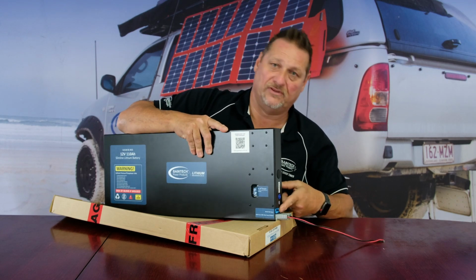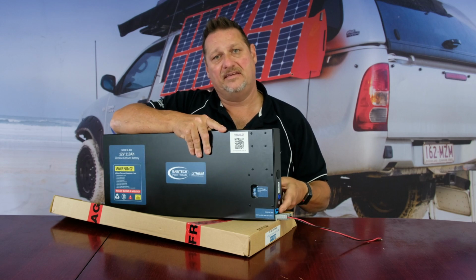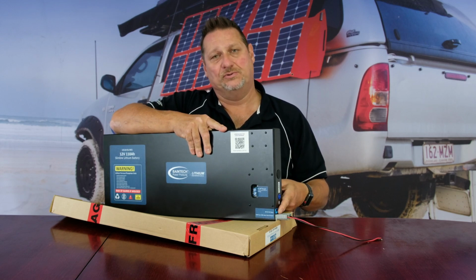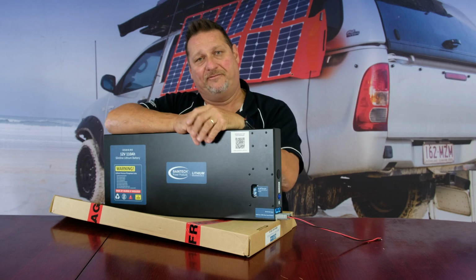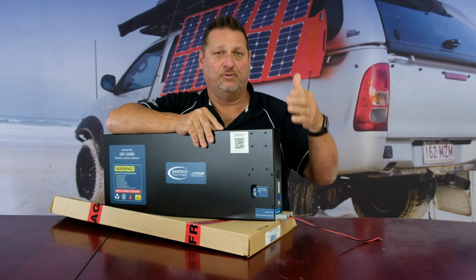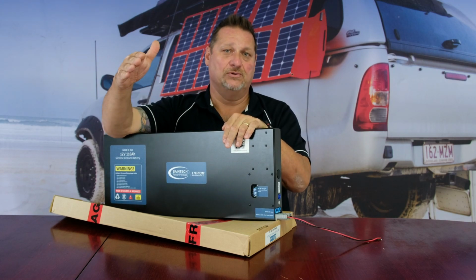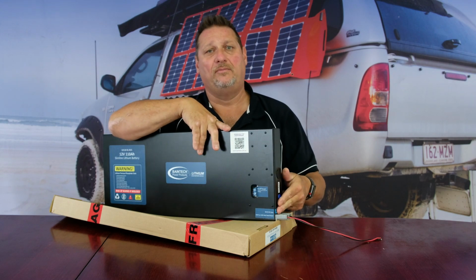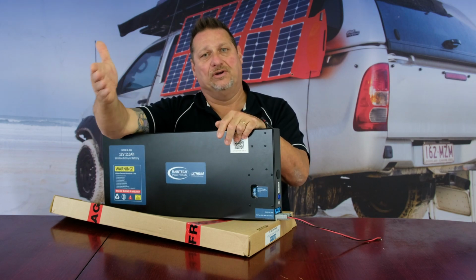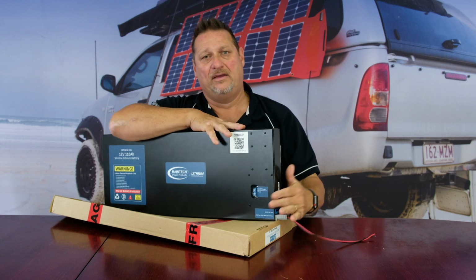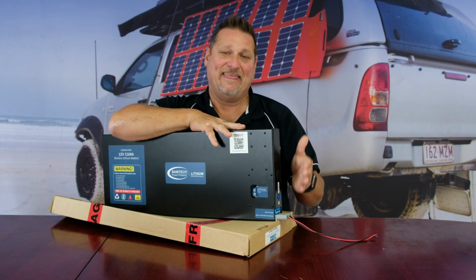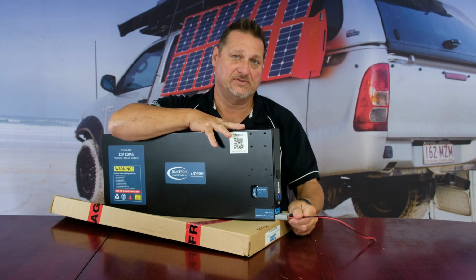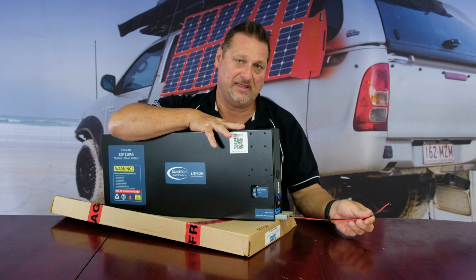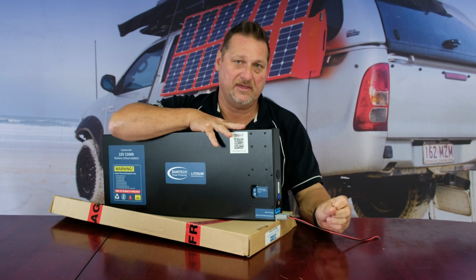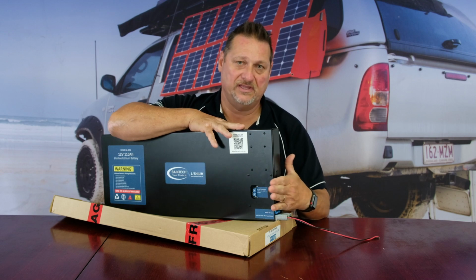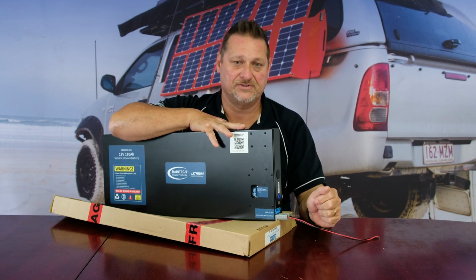On the internal side of this unit, because we do have the DC to DC in here, it's still advisable to put an external fuse or circuit breaker on the input line, closer to your cranking battery or wherever you're pulling the power from. This protects that circuit from the battery supplying power into the charger. That particular circuit is not on the same circuit as the output of the battery. This is purely the output side, which is covered via the BMS if there's a short. On the input side, that would still have to be an external fuse.